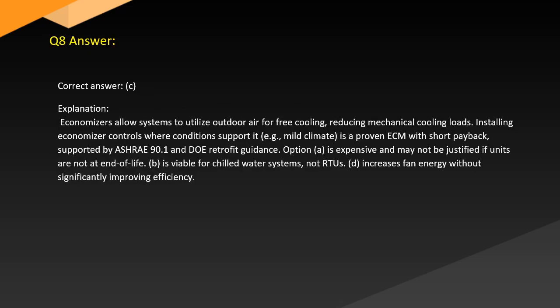Answer. Correct answer: C. Explanation. Economizers allow systems to utilize outdoor air for free cooling, reducing mechanical cooling loads. Installing economizer controls where conditions support it, e.g. a mild climate, is a proven energy conservation measure with short payback, supported by ASHRAE 90.1 and DOE retrofit guidance. Option A is expensive and may not be justified if units are not at end of life. B is viable for chilled water systems, not RTUs. D increases fan energy without significantly improving efficiency.